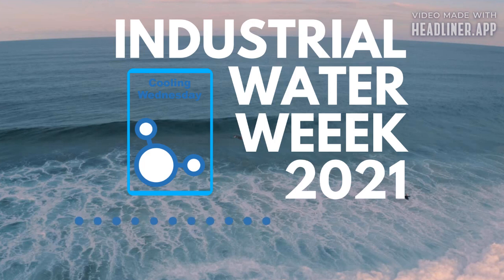The difference between the entering hot water and leaving cold water in a cooling tower is called this. What is the cooling tower range? A chiller ton is how many BTUs? What is 12,000 BTUs? A chiller ton is 12,000 BTUs, where a tower ton is 15,000 BTUs. They add an extra 3,000 BTUs for the parasitic heat that the chiller makes.